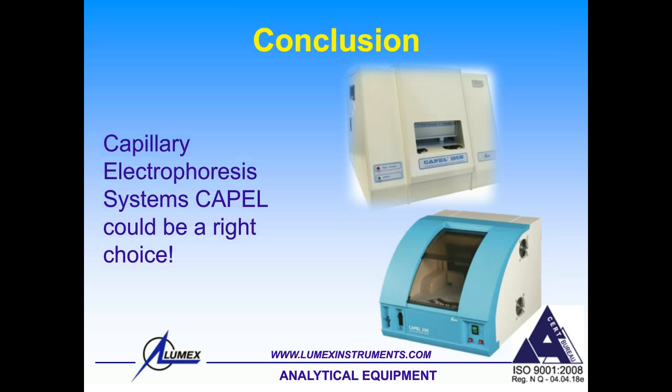Now I'm ready for any questions. One question is how the capillary temperature is controlled. The capillary is thermostated with liquid — normal deionized water — and the temperature is controlled by a Peltier element. Another question: can you have several capillary cassettes with capillaries of different lengths to switch between short-time analysis and high-resolution analysis, and how fast can the cassette be exchanged?